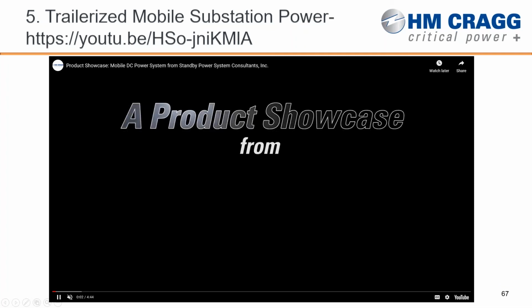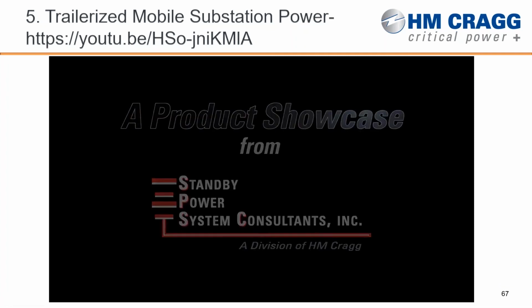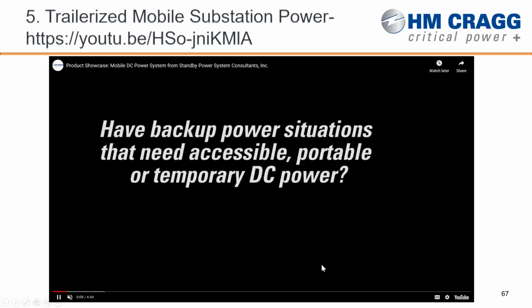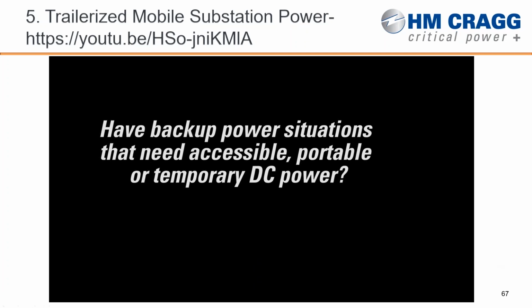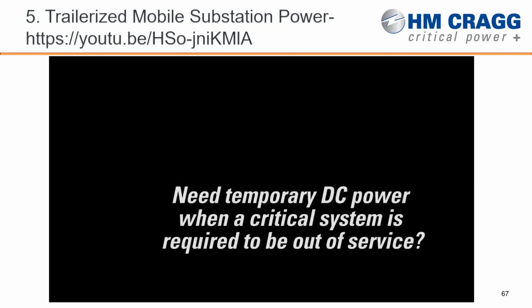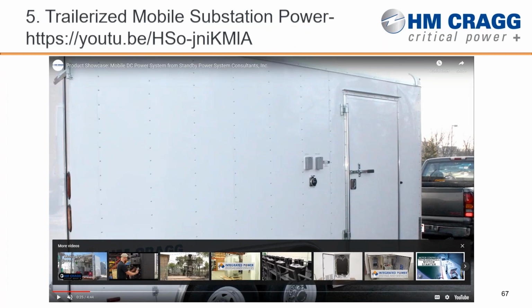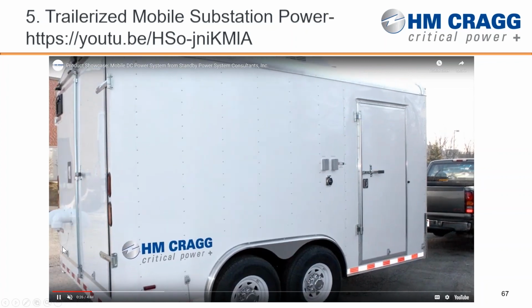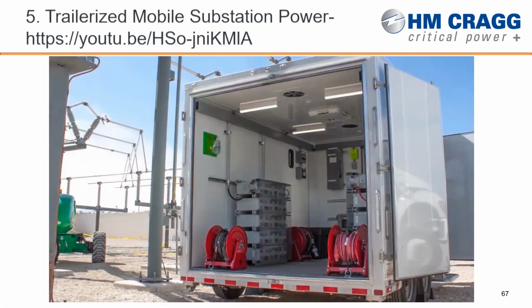I actually had the opportunity to go down to Chicago and help with assembly on this particular trailer you're going to see here. We really want to utilize this with all of our partners. Right now it's a big hit in Chicago with our SPSC customers for utility substations and telecom services. This creates a temporary power source for DC type applications where you need to service your switchgear or other DC powered equipment, and you have no real good way on site to keep the loads powered. So utility companies will take these power trailers and hook them up to their systems before they tear down or take down the on-site power devices.